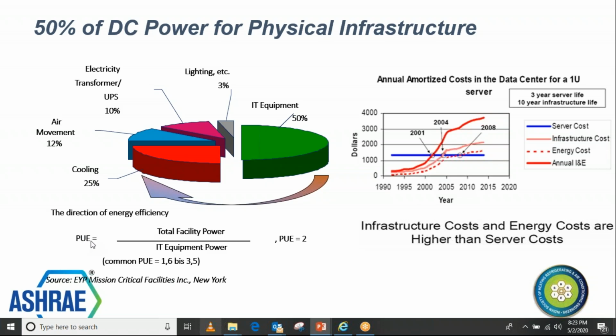So that is known as the PUE, power usage effectiveness, which means total facility power. When you add the power of all these components together, then divide that power by the IT equipment power, it means that when the IT equipment power increases, your PUE factor will come down, and the lower the PUE, the better the data center energy efficiency. PUE is the reverse of data center energy efficiency. So the focus is basically to reduce this portion and increase this portion. So how will you reduce this portion? You can see here that air movement and the cooling mechanical is using the maximum power. The maximum power is consumed here, not here, compared to the overall.